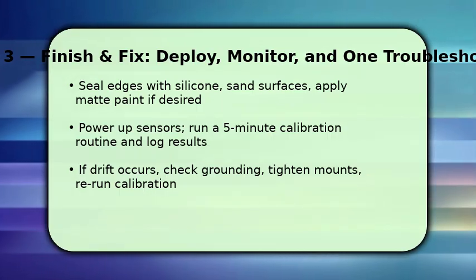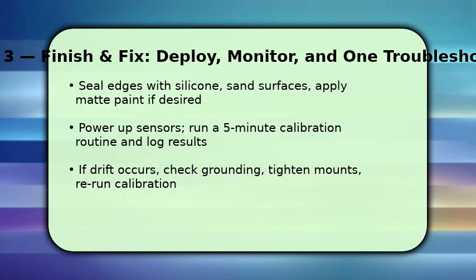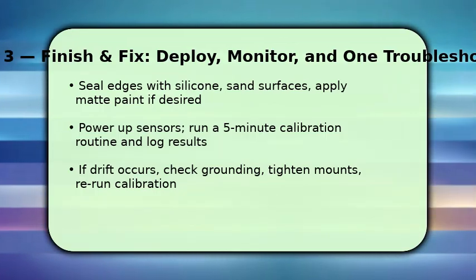Watch for steady readings. If you see drift or noise, check grounding and shielding, tighten loose mounts, and isolate vibration sources, then rerun calibration. If problems persist, swap one component at a time to identify the fault.